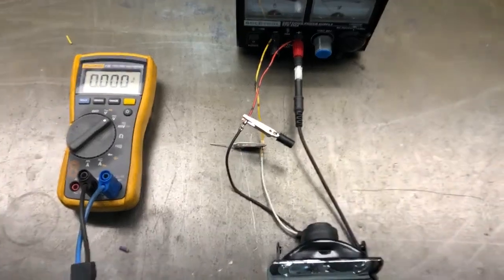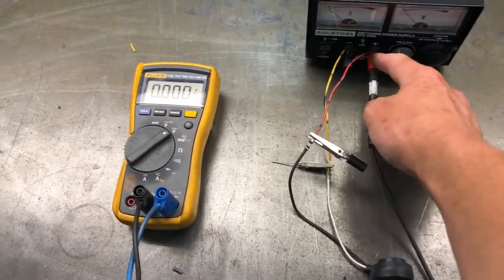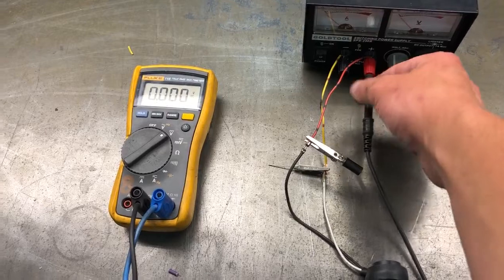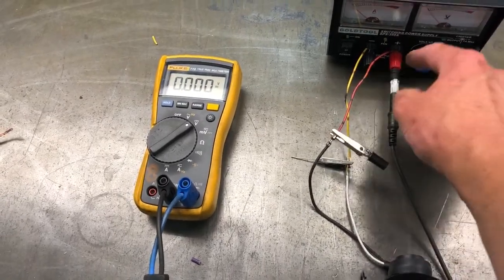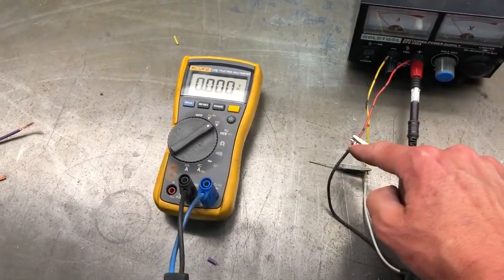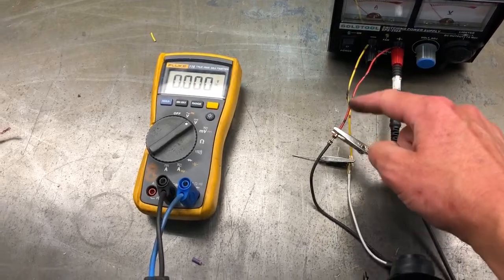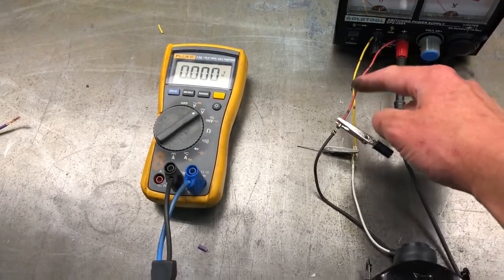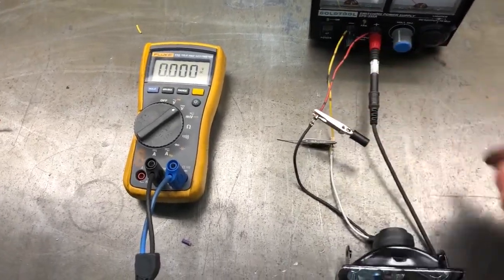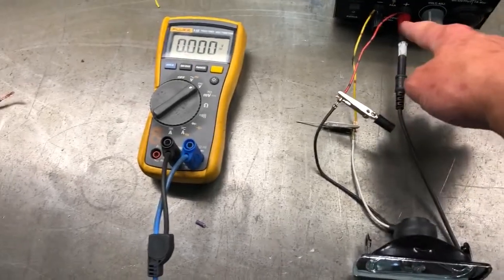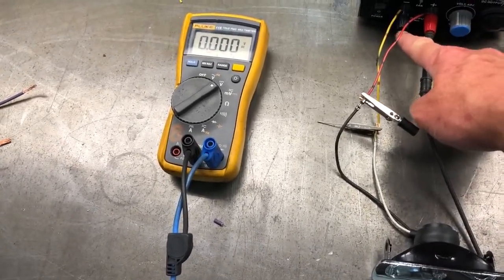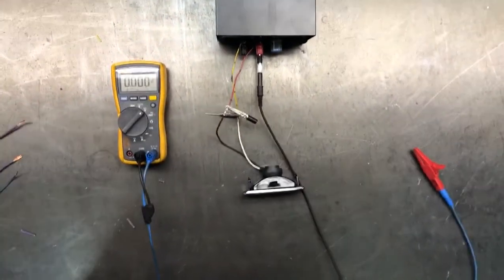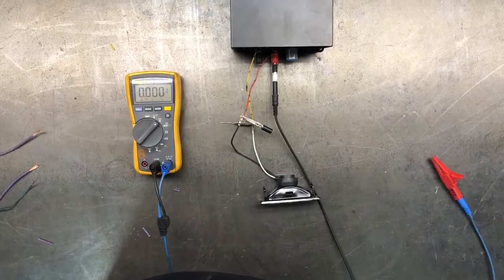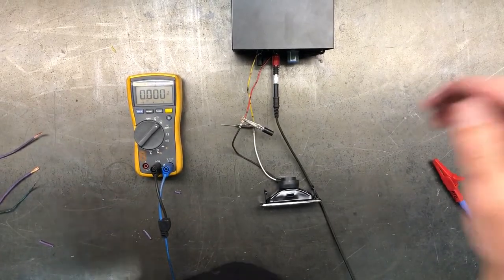So I've got my one probe on my positive here. When I'm checking for voltage drop in this wire, I'm gonna probe here, and that'll give me the difference, or what is being dropped or eaten up within this wire. If I went from here to here, all that's telling me is the difference from positive and negative on this unit. So I'm gonna set the camera up here. We're gonna get this test rolling and see what we find.